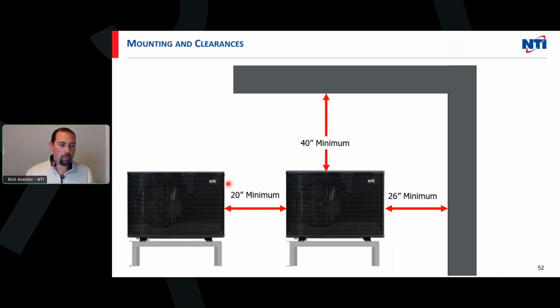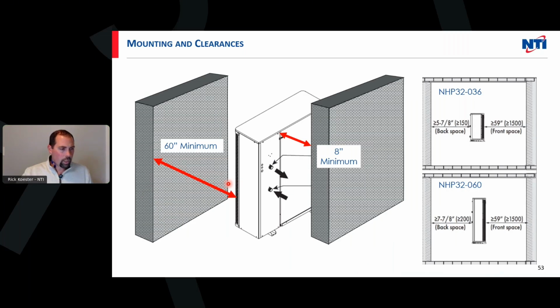Overhangs above them, we want to have about 40 inches of minimum space. And again, that's going to be for airflow mostly, right? We want to make sure we got good air coming through these things so they can breathe, and we can transfer that into the refrigerant and then the water. Any wall in front or below or behind it, we want 8 inches behind it, minimum 60 inches, about 5 feet in front of it. So again, mostly airflow, and a lot of times we can't help this.